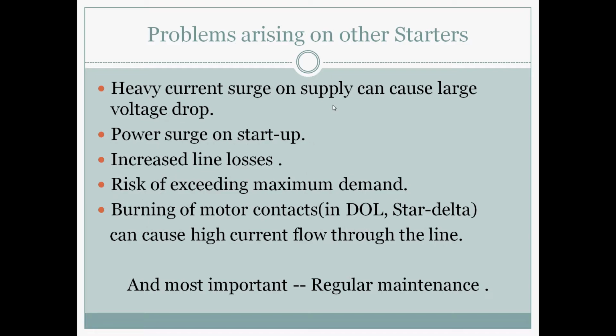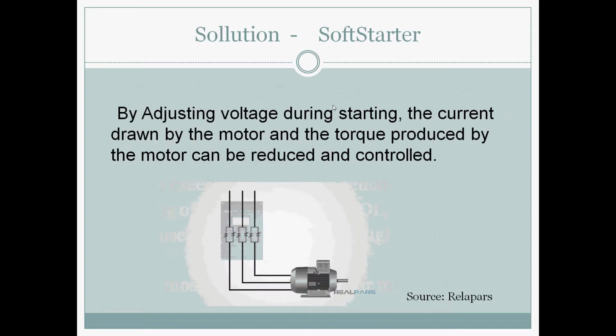But the problem arising with a DOL starter, meaning direct online starter, is that the heavy current surge on the supply can cause a large voltage drop. Next thing is power surge. While starting, the starter requires a star connection, then going to running, it requires delta. So there is a huge change of voltage and current, a power surge, increased line losses due to that, and risk of exceeding maximum demand. Again, burning of motor contacts happens mostly in DOL and star delta, and it can cause high current flow throughout the line. And most important, it requires regular maintenance for the motor contactors.